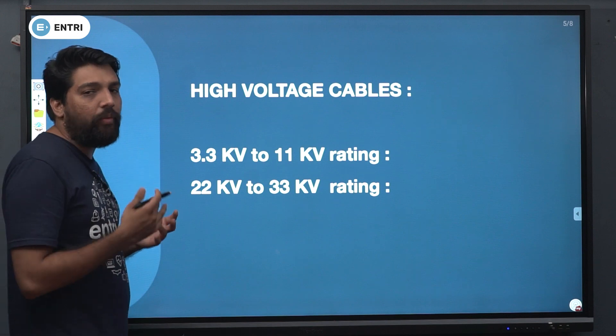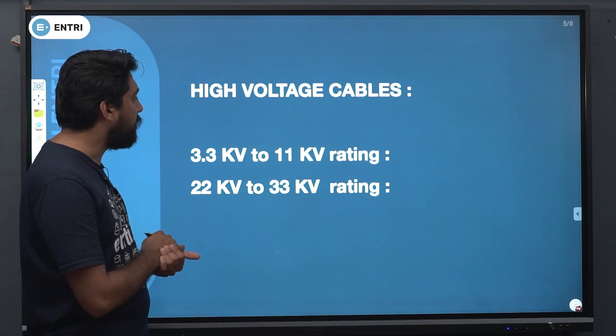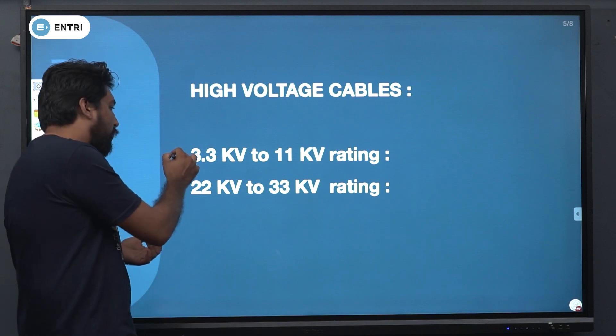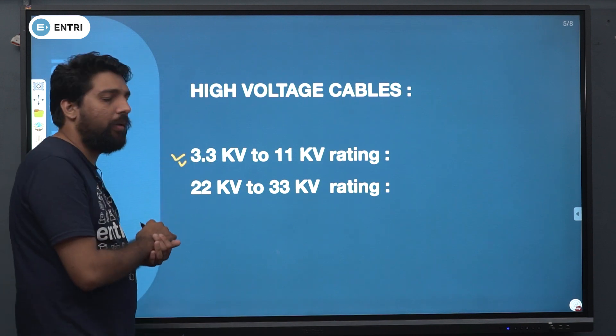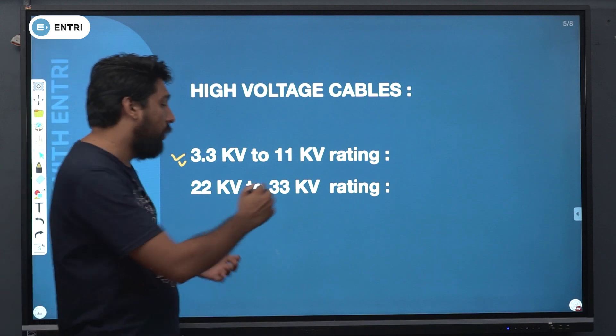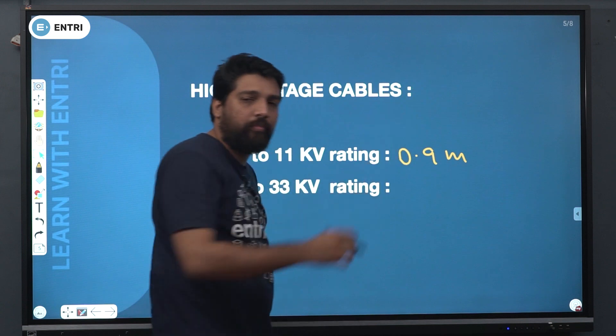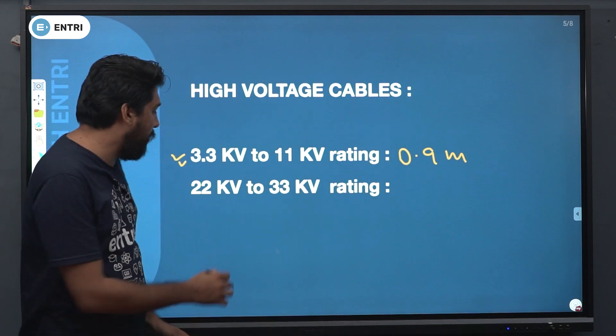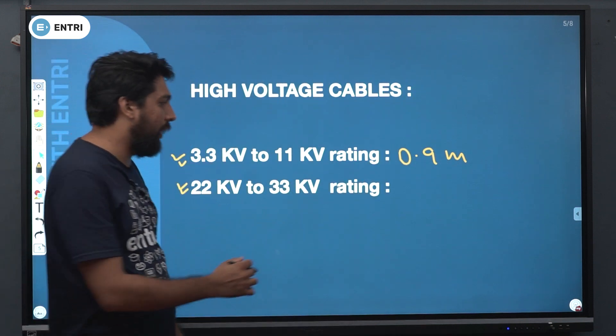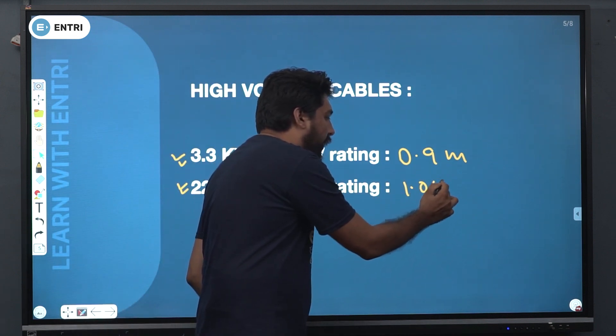This is the concept of high voltage cables. In high voltage cables, 3.3 kV to 11 kV, the depth is 0.9 meters. At 22 kV to 33 kV, the depth is 1.05 meters.